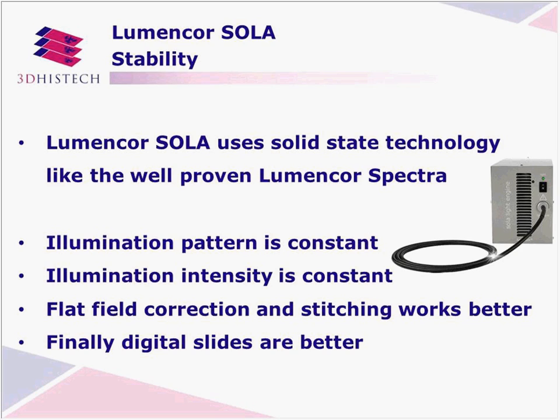Due to the solid state illumination, the illumination pattern is always constant during image acquisition. The intensity is always constant. So what are the advantages? If the illumination pattern and the intensity are constant, the background correction of the system works better, and with the background correction working better, stitching also works better. So finally the digitized slide will be better.